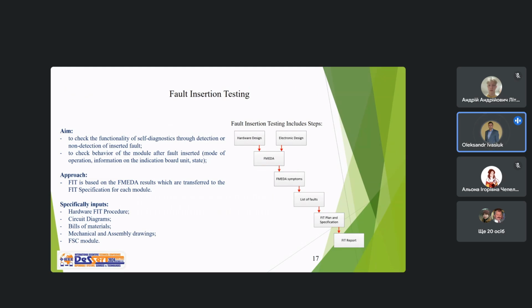What does that mean? It means the module should be given a single hardware fault, and after the fault has been activated, the tester must record the obtained result and compare it against expected results.